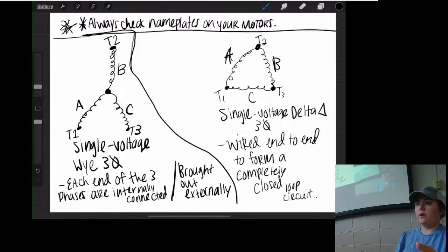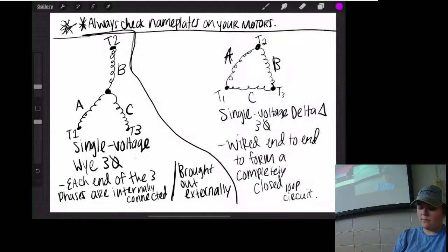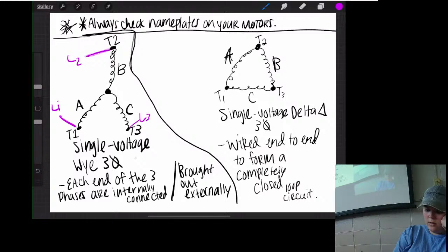This is a single voltage Y three-phase motor, so each end of the three phases are internally connected and brought out externally. Your T1 would go to L1, your T2 would come out here and go to L2, your T3 would come out here and go to L3. That's why it's a single voltage Y three-phase motor. And since this is a Y, if you wanted it to go to, say, 480, that's what you would have.